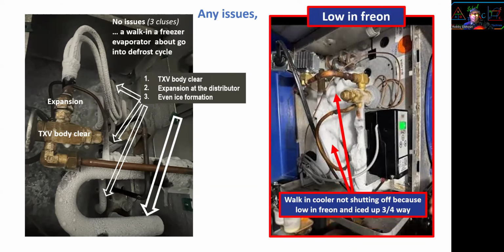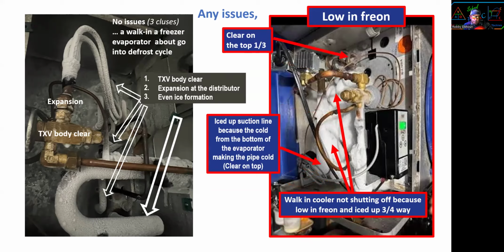This one is low in Freon. Why? Because the walk-in cooler is not shutting off because it's low in Freon, and there's ice three-quarters of the way. Clear top third, ice. The ice is built up on the suction line, not because the suction line is frozen, but because the ice from the evaporator is freezing the suction line. Right? The suction line is not frozen from the inside because it's above 32 degrees. There's no ice on top. Suction line at the end of the evaporator is frozen just because the cold from the ice is making the suction line frozen.